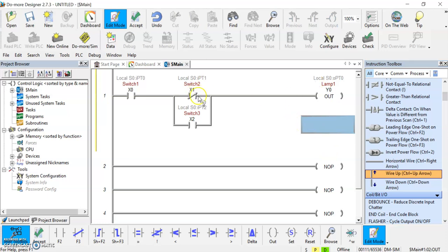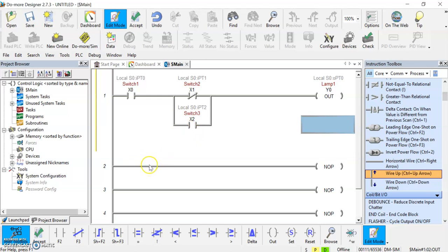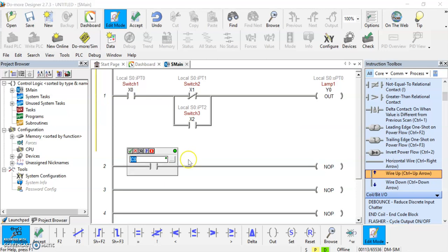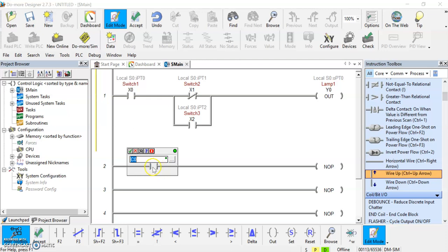Very interesting. This would be a very simple program here. Let's take a look at how we could also do something with an internal bit. Let's take a quick look at our second rung and let's populate that. We'll put another normally open contact here, and we're going to assign that not as an input but as an output. You're probably wondering, well, these normally open or normally closed are always associated with input, so it doesn't have to be that way in a PLC program. This is basically just saying, hey, if this is a 1, then this is going to be activated as a 1, and this is looking for a 1. So when this sees a 1, it's going to go into its true state.